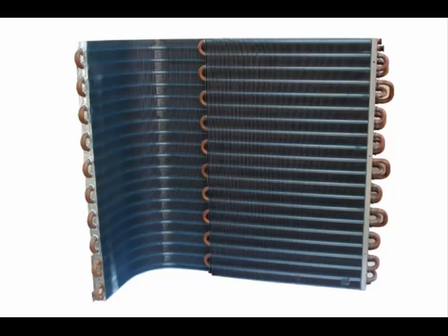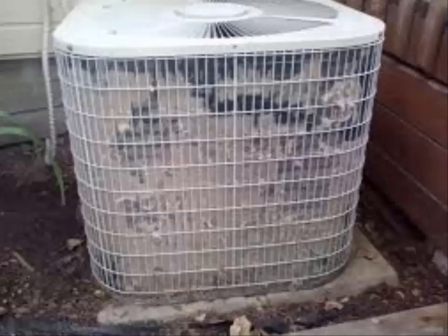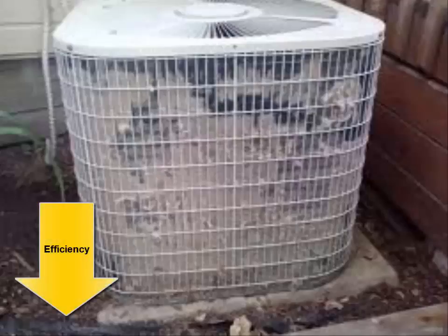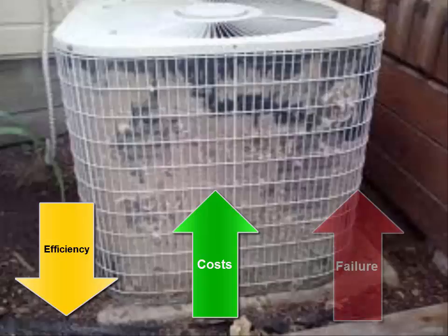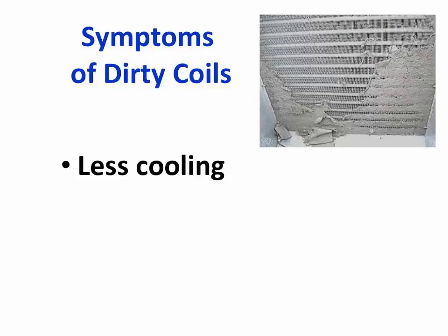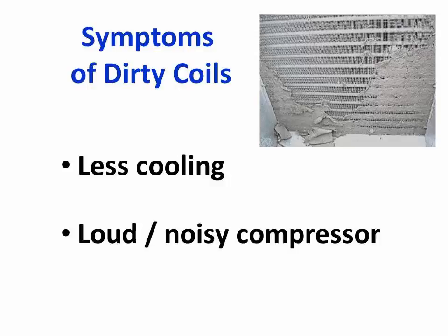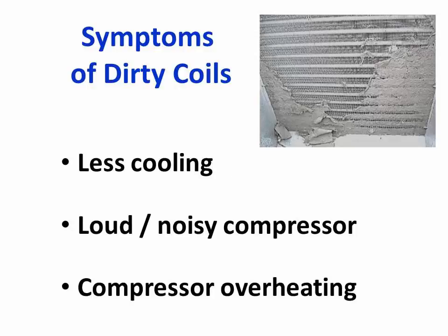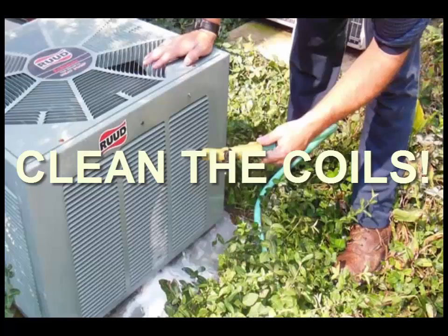The coils are the part of your system where the actual heat transfer occurs. Anything that insulates them will reduce your system's efficiency, increase operating cost, and increase the likelihood of equipment failure. If you find your compressor keeps getting louder with each passing month, or that the compressor is overheating and turning itself off, leaving just the fan still running, cleaning the coils is a great place to start to remedy the situation. Let's start with the basics.